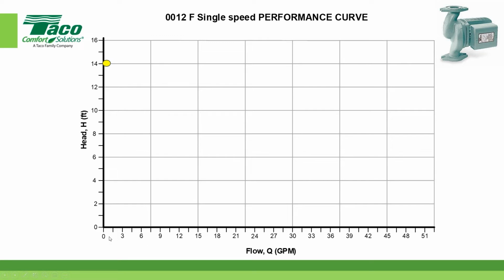At 0 flow going this way, I have a resistance, or feet of head, at 14. Okay, so that means it's going up to the top of the pipe. It's coming up right at the top of a 14-foot pipe, and it's holding there with just a little bit at the brim. That means it's pushed that water up that high. That's what I want you to think about. It's actually the differential pressure from whatever's on the inlet side to the pump, but it's as if it raised that water 14 foot, and then stopped right there. Based on that circulator at that RPM, at that horsepower, etc., that's what it has the capability of doing.